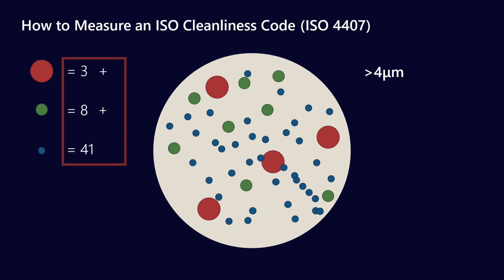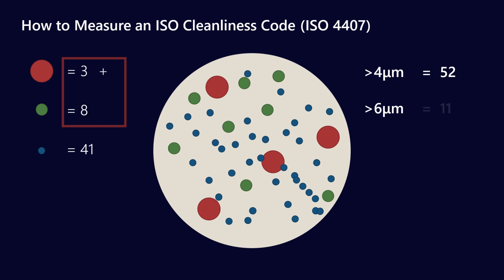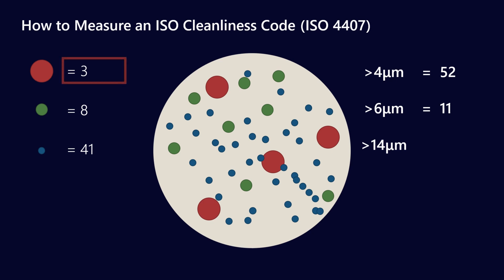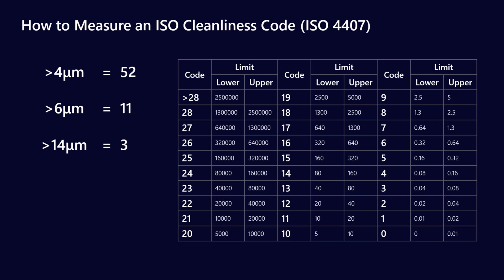Above 4 micron, you add all three of those numbers together to give a total of 52 particles. Above 6 micron, you add the two larger size groups to give 11. And for the 14 micron count, you just take the largest group, giving 3. That gives three numbers — 52, 11, and 3 — which you then match with the ISO cleanliness spec to get your ISO cleanliness code.